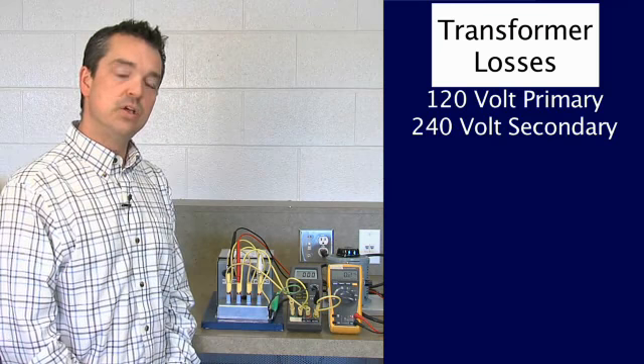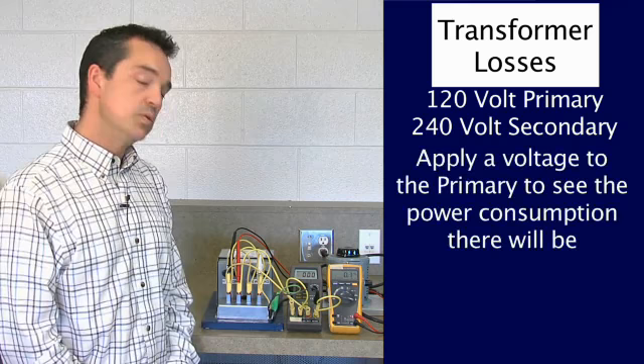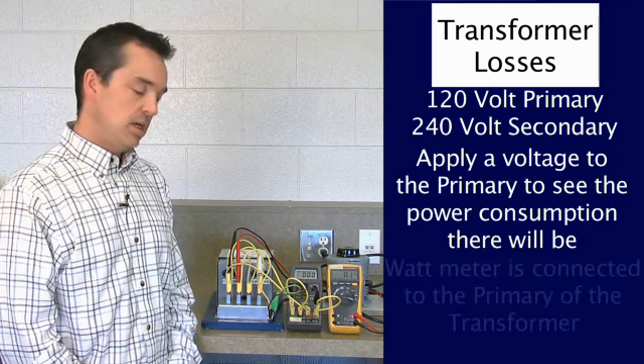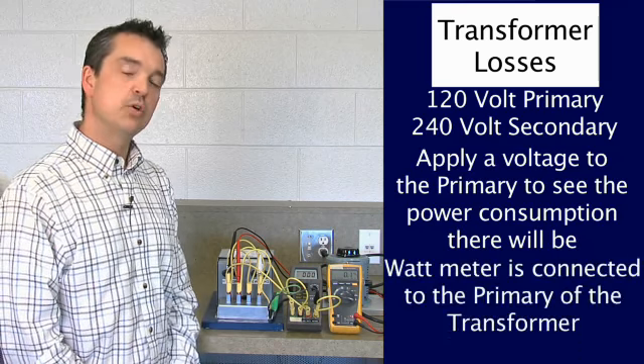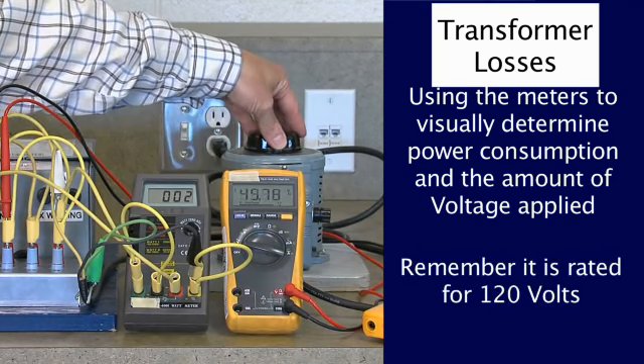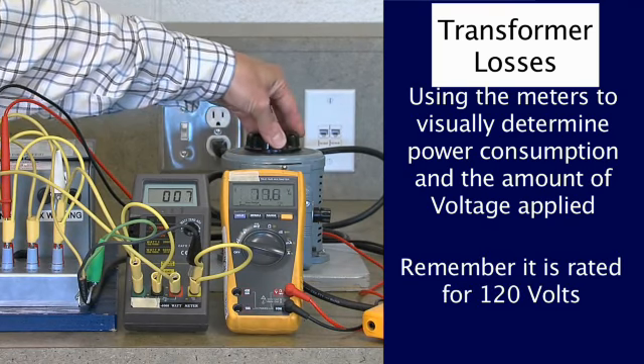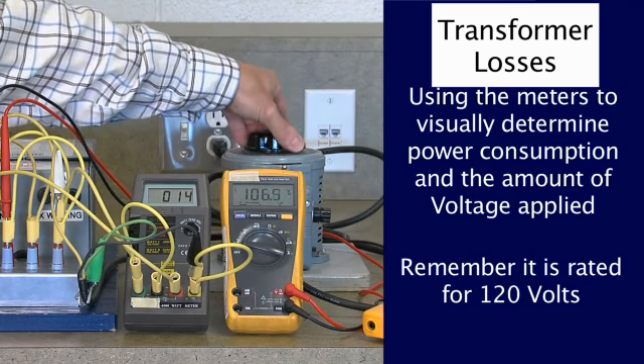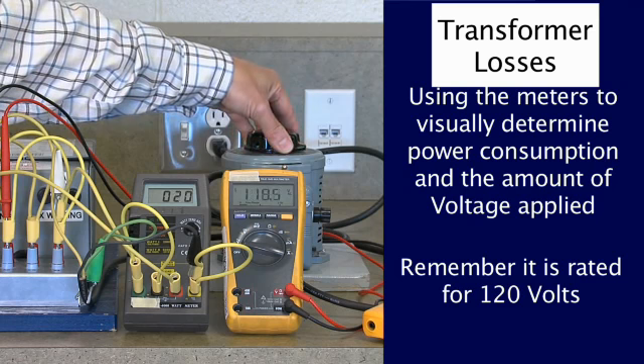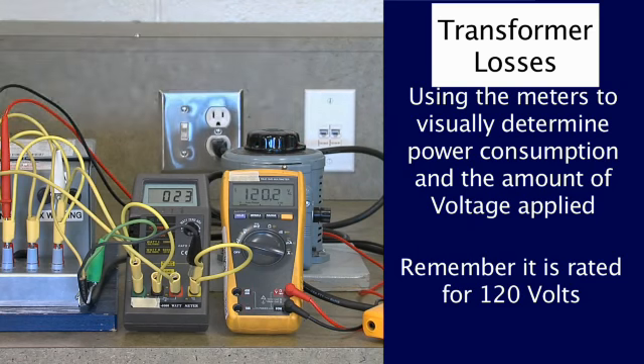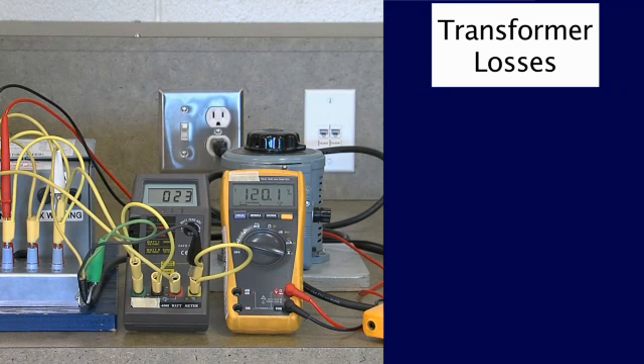So the first step in doing the open circuit test is to apply a voltage to the primary to see what kind of power consumption I will have. And we're going to determine whether this is a core loss test or a copper loss test very quickly. So what I'm going to do is apply this voltage. And what I'm looking to see on these meters is what kind of power consumption will I see and what kind of voltage can I take it up to. Remember, it's rated for 120 volts. So you can see on my voltmeter, the voltage is climbing as I turn up the variac. So I have now applied 120 volts to this transformer primary, and it's rated for 120 volts.